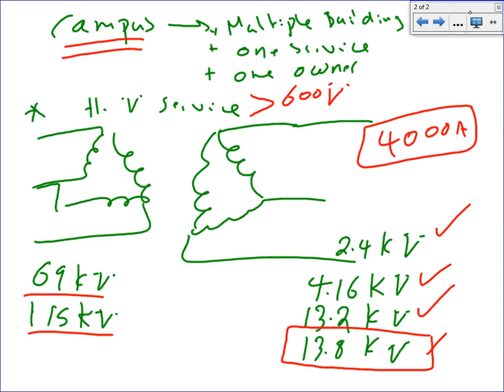Because remember, if you are at the U of M and you have multiple buildings everywhere, what they do, guys, is they have a medium voltage substation, 13.8. So this transformer lands into a big fat medium voltage switchgear, 13.8. They have a feeder that goes to building A, 2 miles away from here. Another feeder goes to building B, 3 miles away from here. And you keep going, all these medium voltage underground. They have tunnels underground, and they push all these 13.8 feeders to go to different buildings.